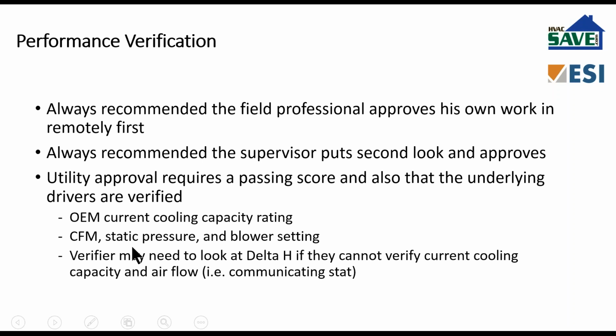They will always verify airflow, CFM, static pressure, blower setting. Again, that's the proper sequence. They're following the same proper sequence that you are. Airflow can be verified remotely fairly conveniently. They don't necessarily need to, but they may look at delta H. Keep in mind that if it's got a passing score, and if they can verify your current cooling capacity and they can verify your airflow, then refrigerant charge must be sufficiently calibrated.